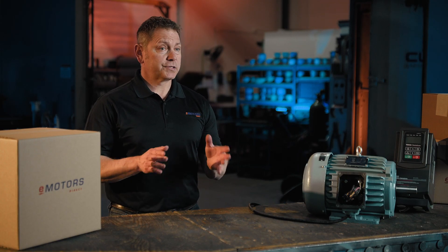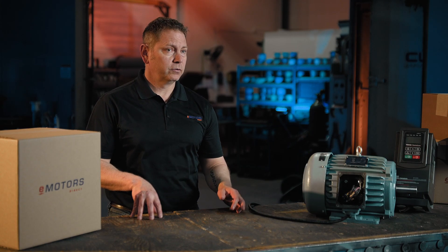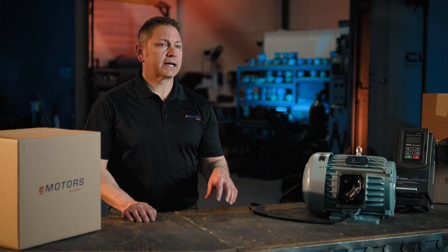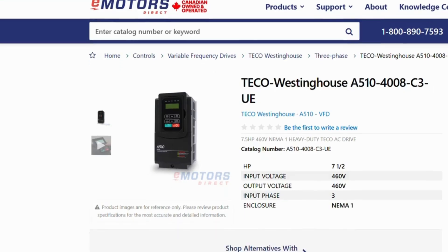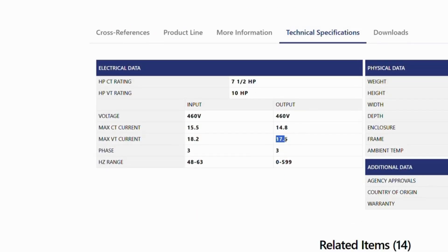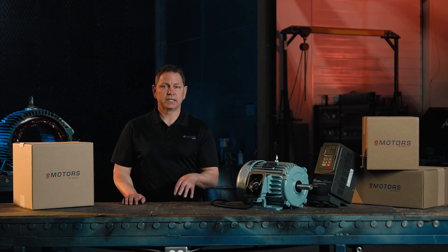For example, if your 7.5 horsepower motor is rated for 9.2 amps at 460 volts and you have a constant torque application, you'll want to ensure the output current of your VFD is more than 9.2 amps. This is usually indicated as max CT current output in the technical section of your data pack. In this example, this TECO A510 is rated for 14.8 amps constant torque and 17.5 amps variable torque, which means you could use it for a 10 horsepower variable torque application because of the reduced overload capacity that is needed.